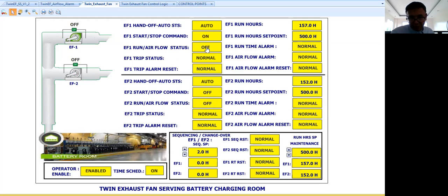Okay, now I have here some time delay. It's around 30 seconds, okay? Before I raise the alarm, I will not do it immediately, okay? I will wait for some time delay. Now the time delay is around 30 or 35 seconds, okay? So after 35 seconds, that's the only time that the alarm will pop up or come into my graphics, okay?